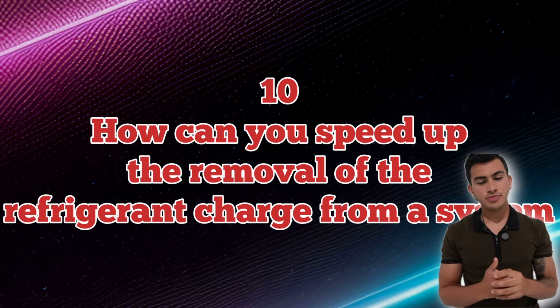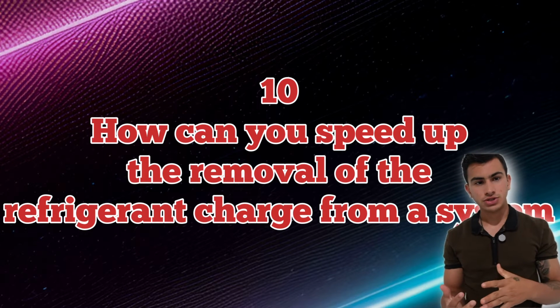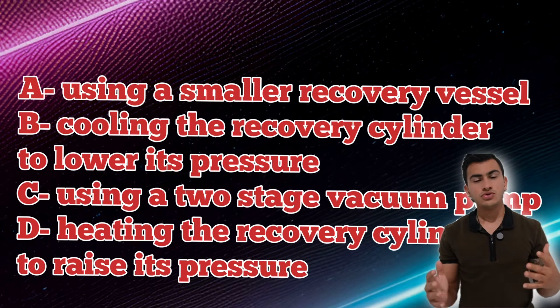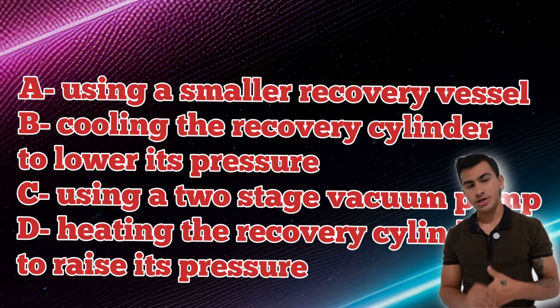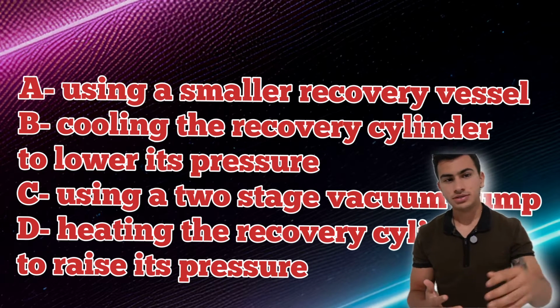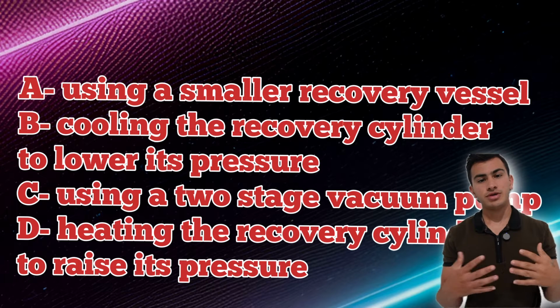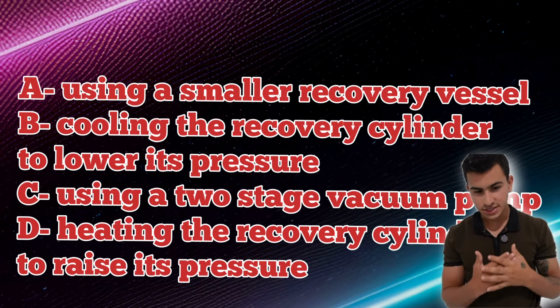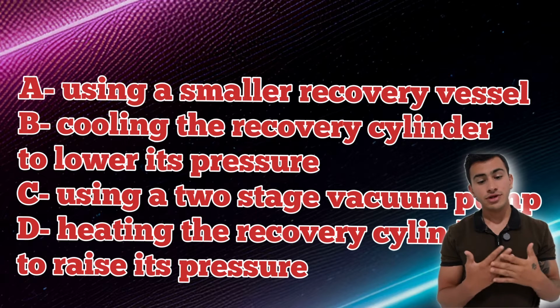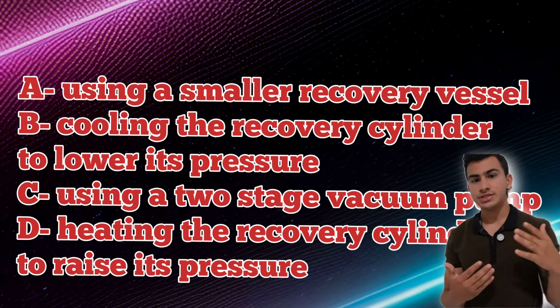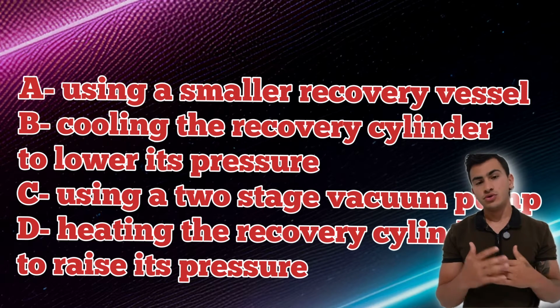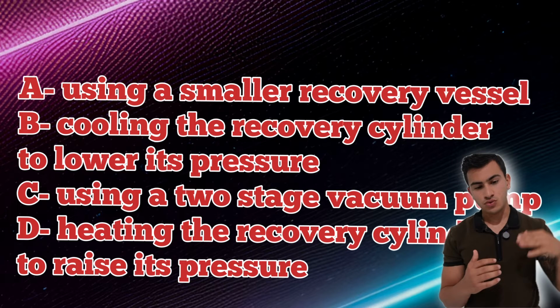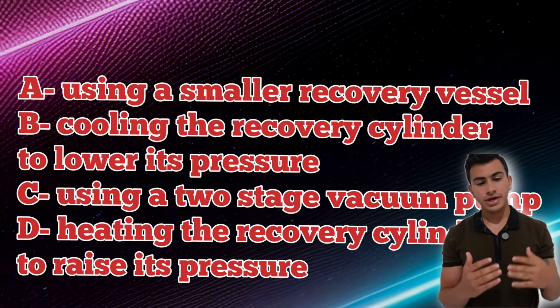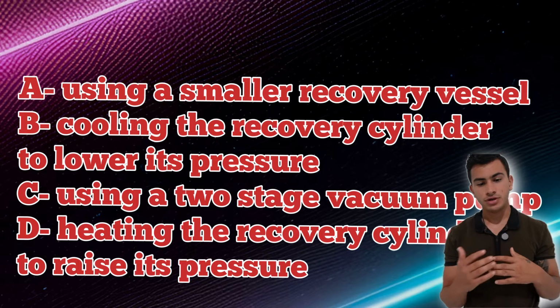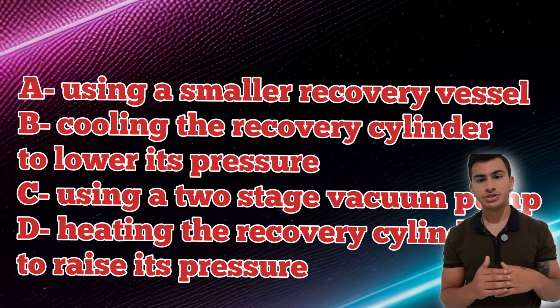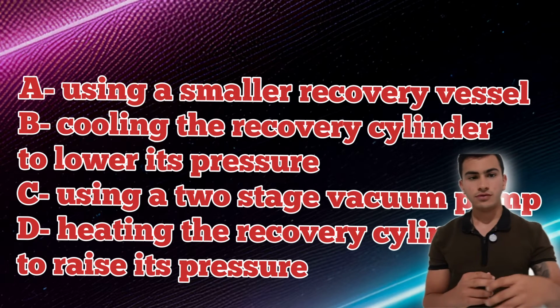How can you speed up the removal of refrigerant charge from a system? Using a smaller recovery vessel. No, that wouldn't make sense. Using a 2-stage vacuum pump. That would not make sense either. Heating the recovery cylinder to raise its pressure. No, you don't want to raise the pressure, you want to lower it. So the right answer will be cooling the recovery cylinder to lower its pressure. So B will be the answer for number 10.